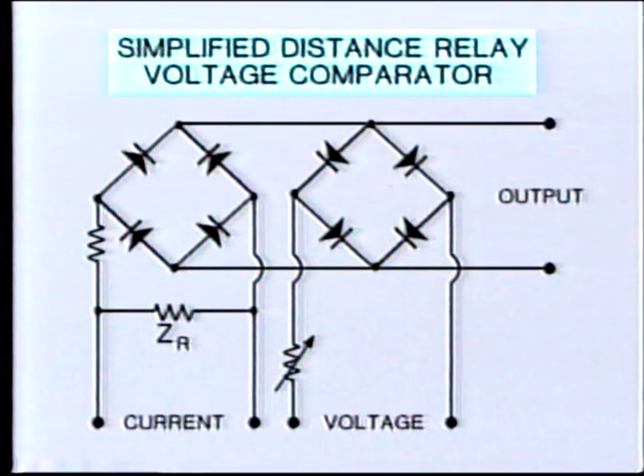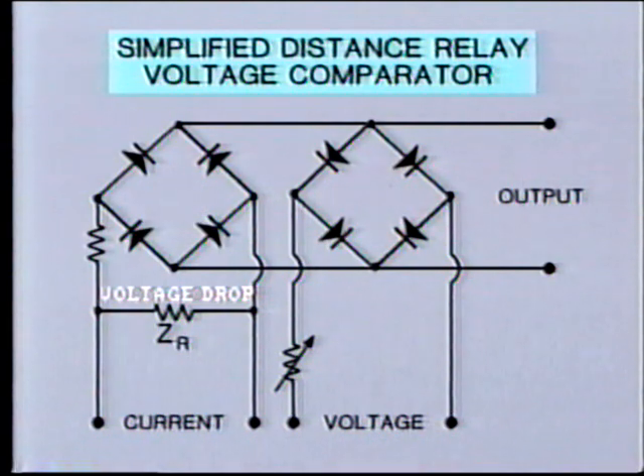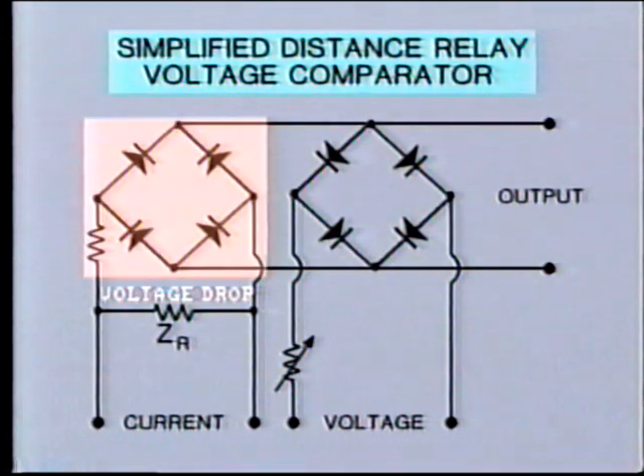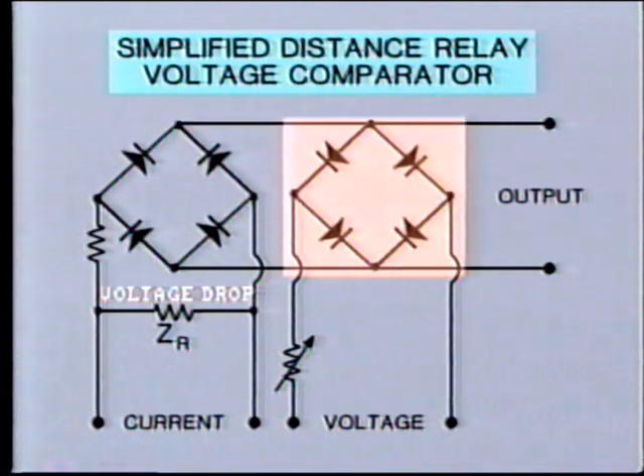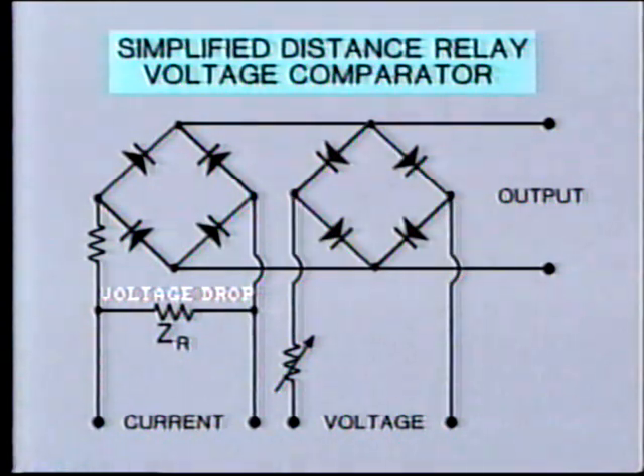For a voltage comparator, the current is passed through a replica impedance, ZR, which is tuned to the same value as the line. The voltage drop across this impedance, IZR, is then fed into the amplitude comparator to be compared with the measured line voltage in the same phase. In other types of relays, equivalent current values are compared.